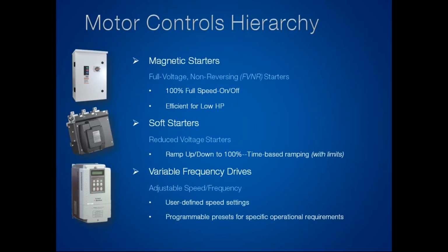The second thing we're going to see are soft starters. Now, in my experience, soft starters are becoming a bit antiquated, but they are still an option for you if you do choose to do so. A soft starter is slowly ramping our motor up to 100%. Think of a soft starter like one of those newer buildings where you walk into a room and the lights kick on. The lights are kind of dim at first, and they slowly get brighter. Essentially, that's exactly what a soft starter is. We don't want to kick that system all on full blast at once. We want that motor to slowly get to where it needs to be based on some sort of time or something like that.